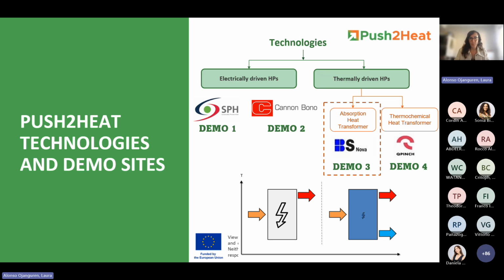But on the other hand, we also have thermally driven heat pumps, and in the Push2Heat project we have 2 different technologies that fall under this category: the absorption heat transformer and the thermochemical heat transformer. Inside, they work differently, but if we look at the outside conditions, the functioning or the basics would be very similar. So in this case, we have 3 different temperature levels.